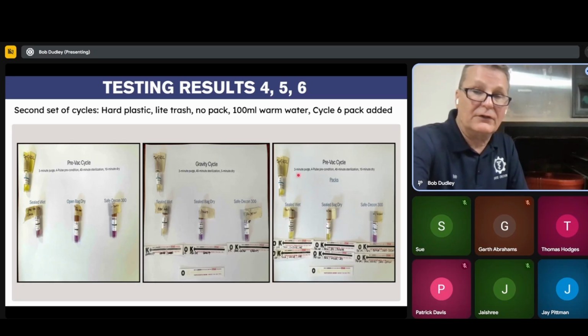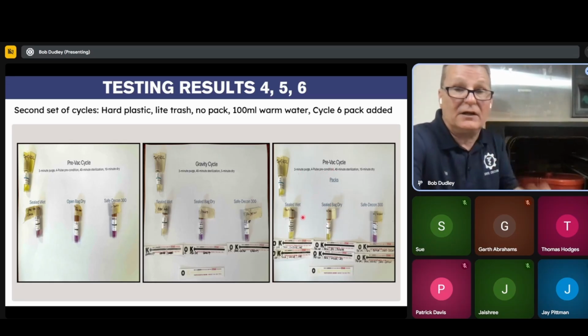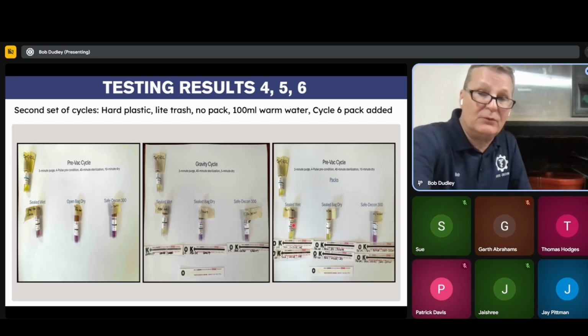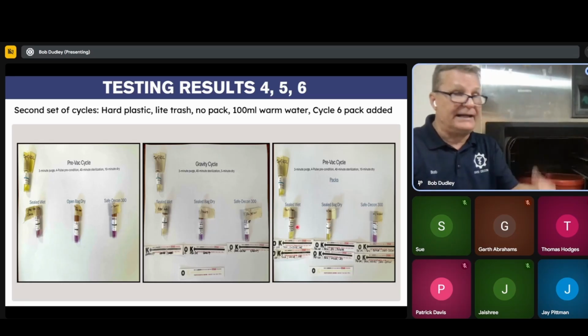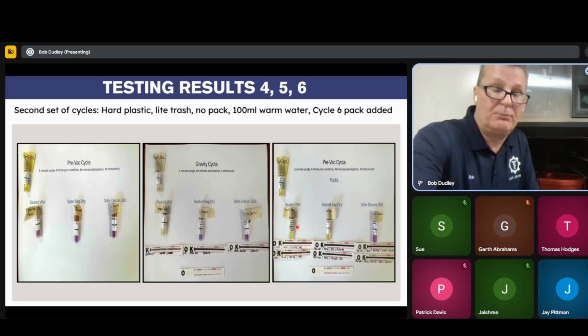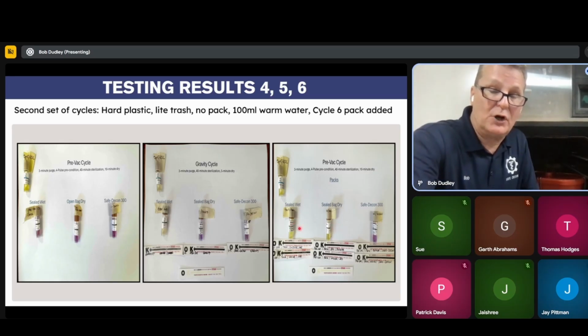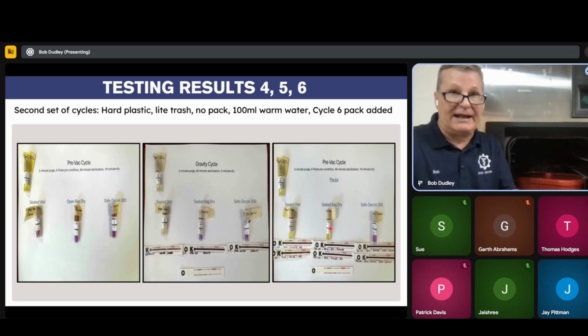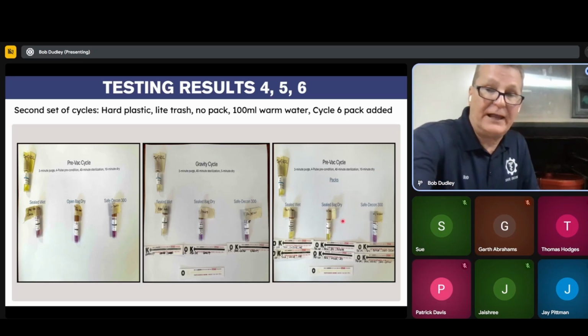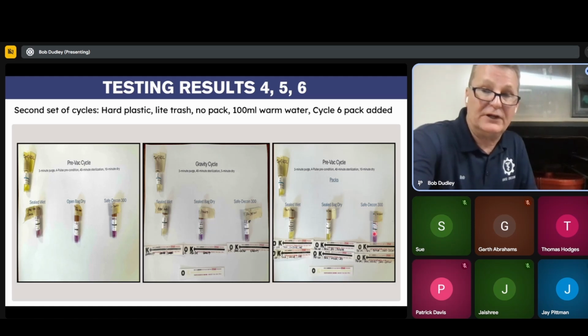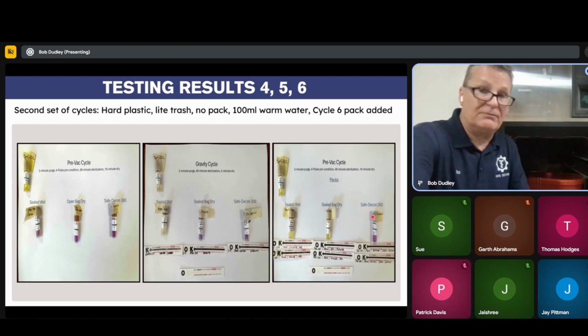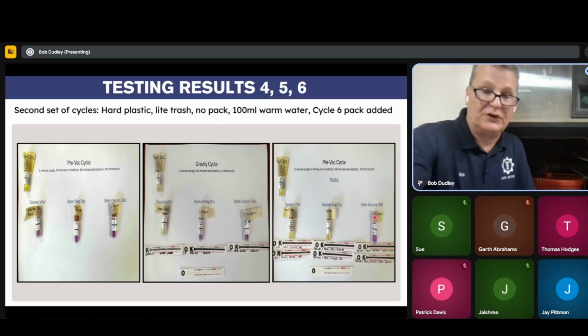We failed on a 40-minute pre-vac cycle with a tight little thing. And what I believe happened with these two is, though this one was sealed, even with water in it, and this one had a little hole in it, they didn't burst until after, my guess is probably the 3rd to 4th pulse. They had burst open, the bag split, but I think it happened later during that pre-vac cycle. And because it didn't have that push and pull, steam couldn't access that bag, so it failed. And the Safe-Decon unit was a champ on this one. It was something that I engineered specifically for this problem here, and we can talk about it another time.